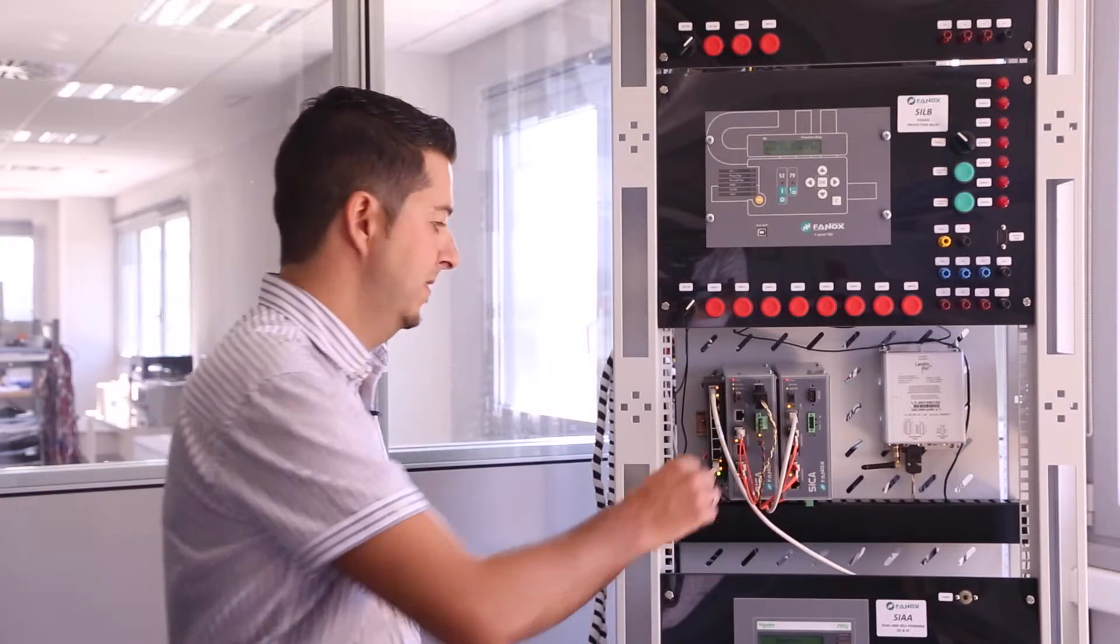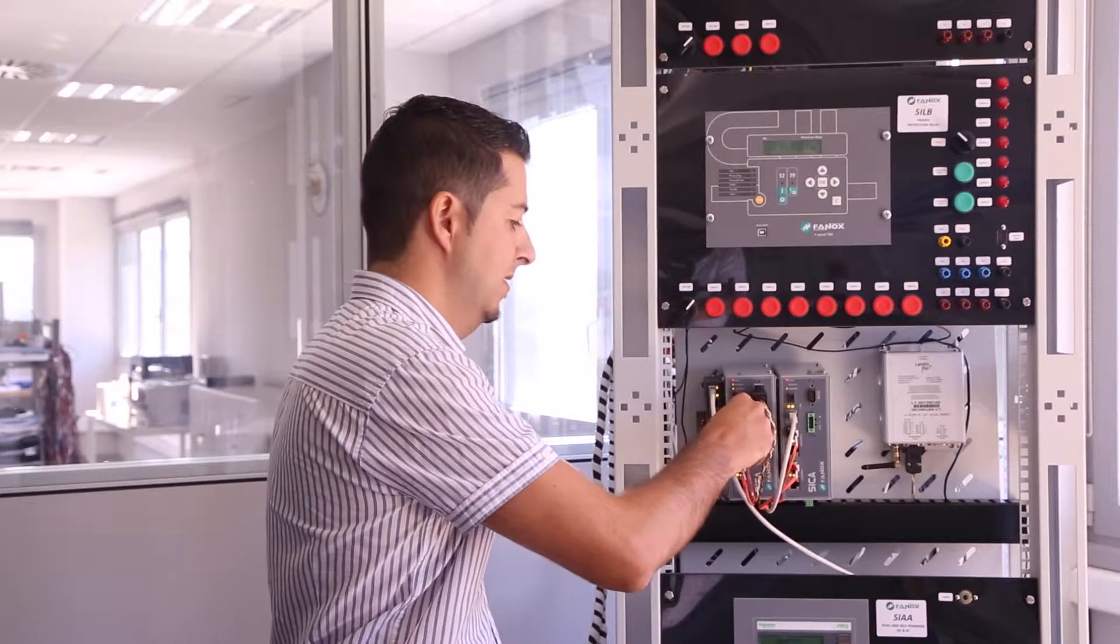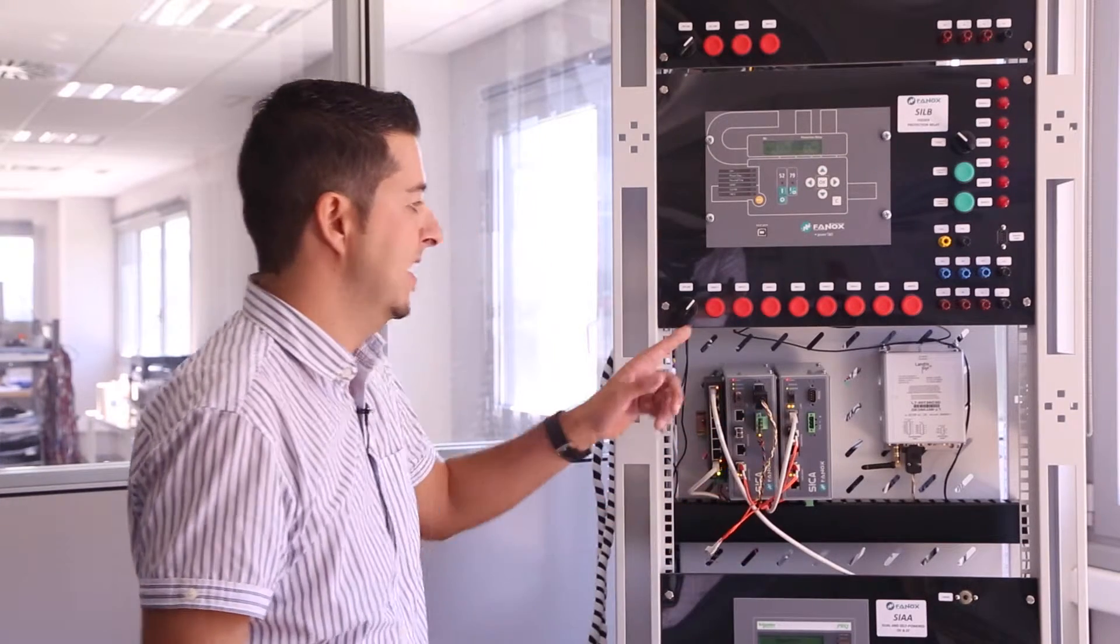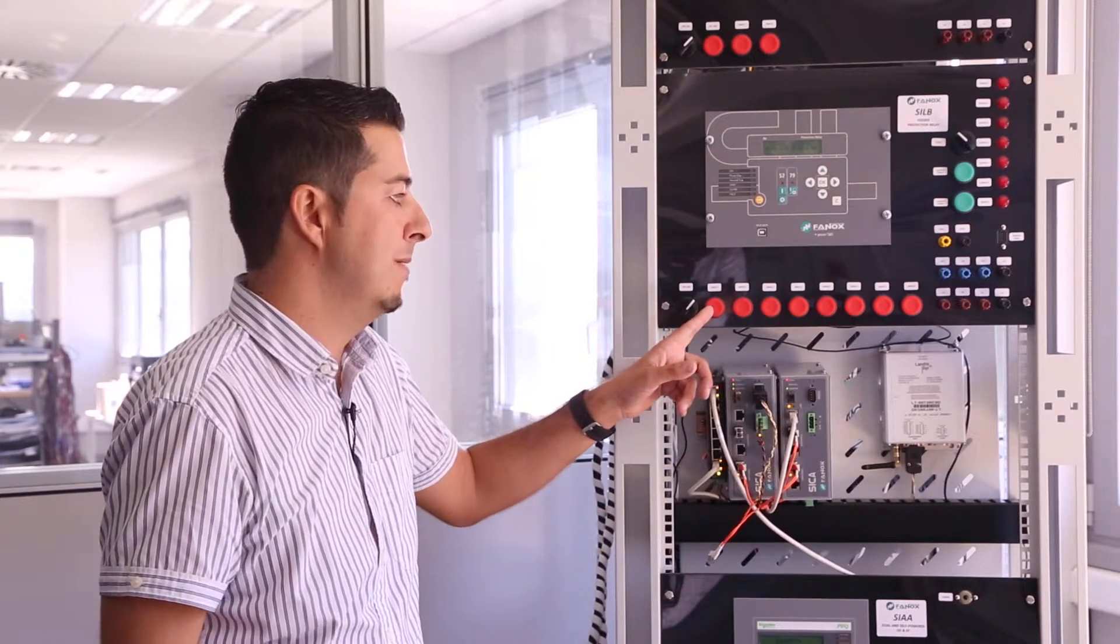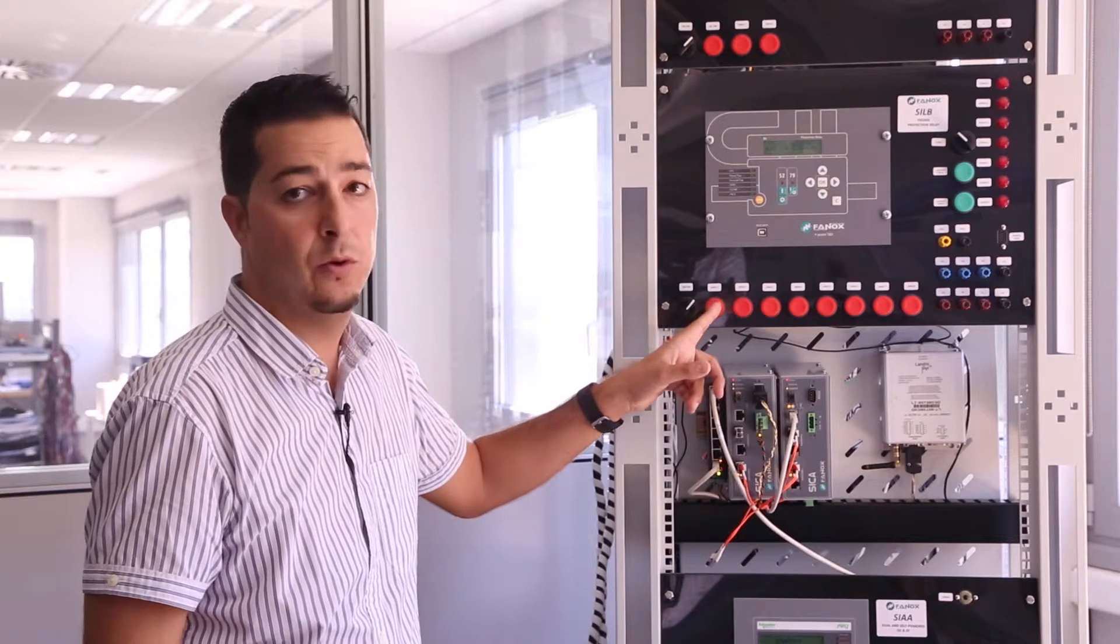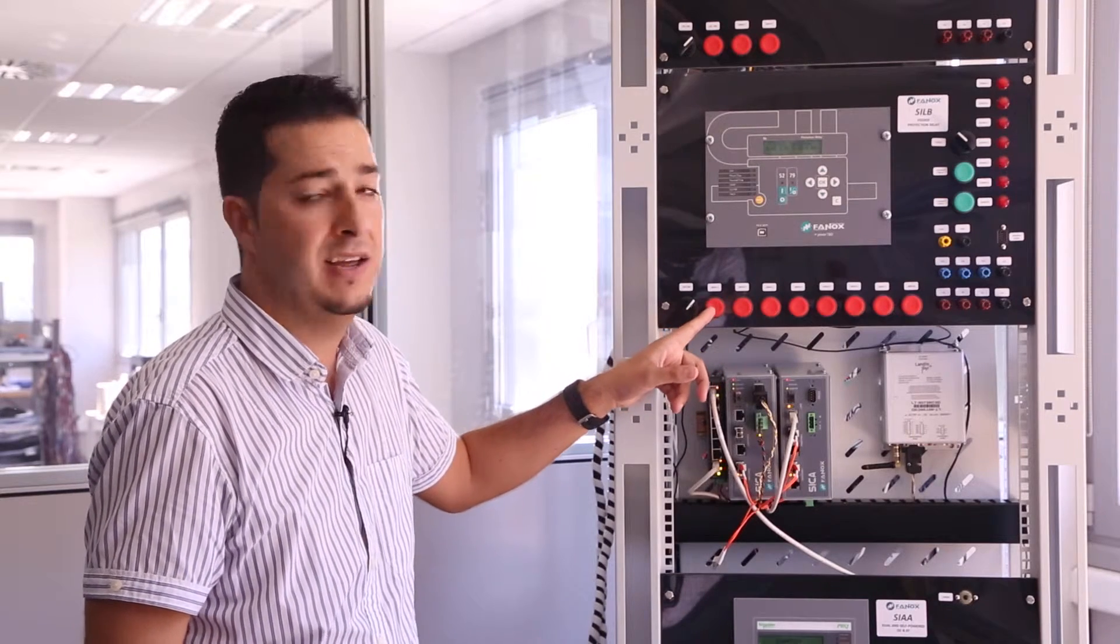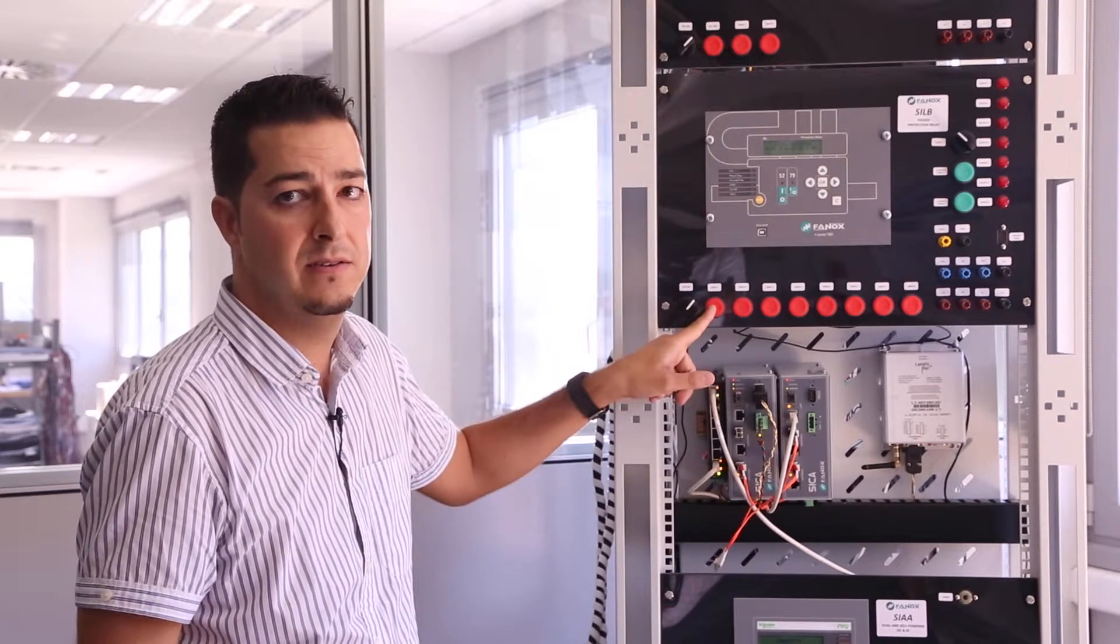We will simulate a network failure by removing a cable from the ring. Then, the GOOSE message that we send, simulating an external trip, should be shown in the network.